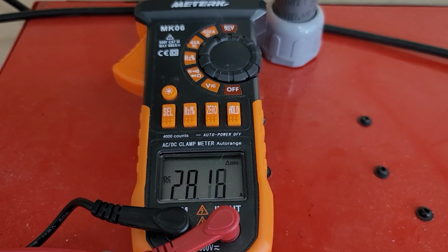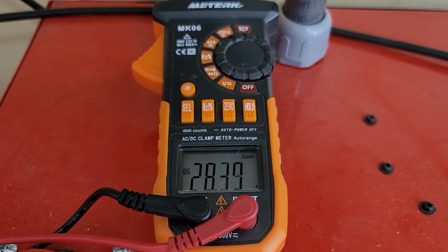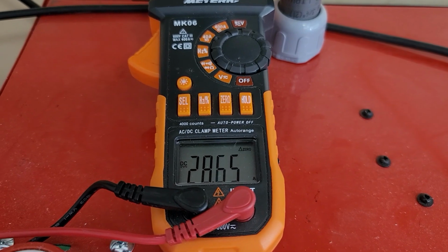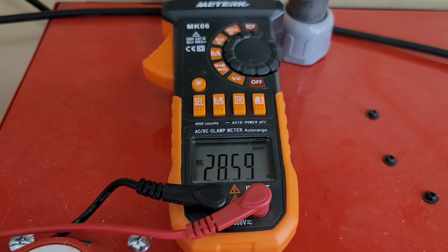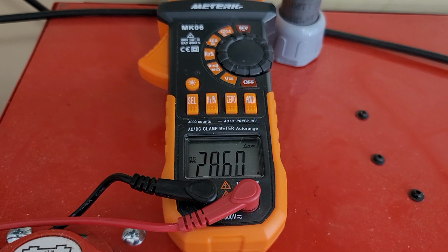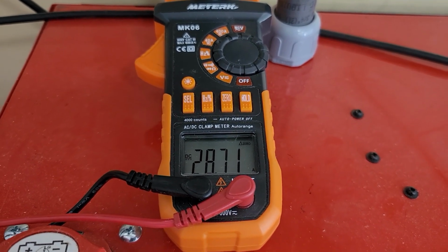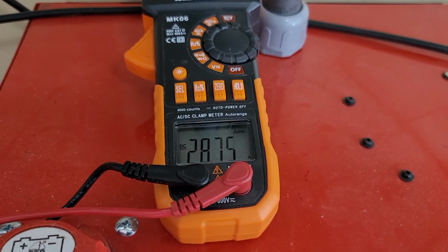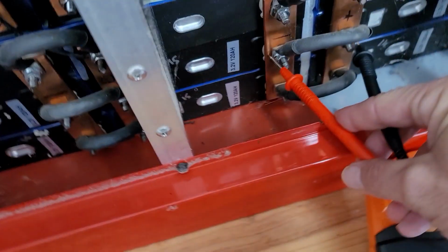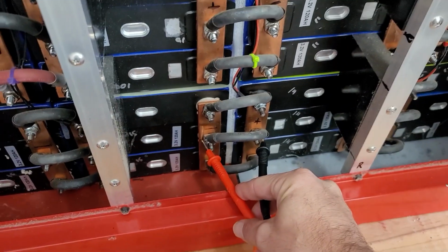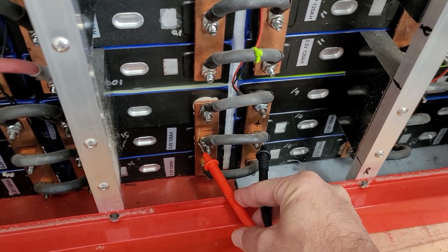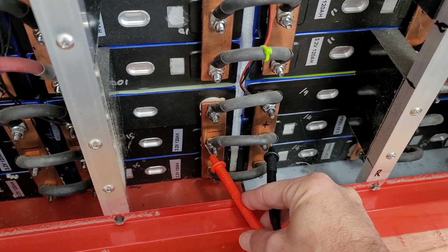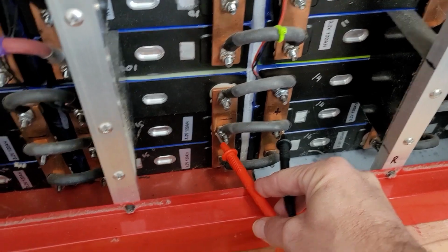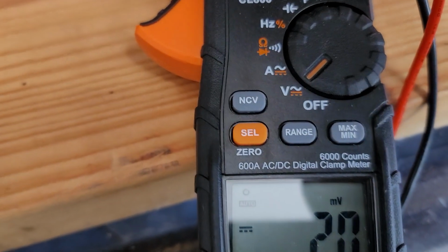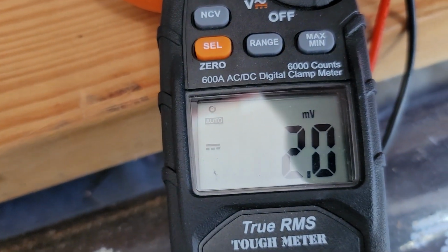At this moment we are up at 28 amp charge for this Powerwall. Let's go take a look at the same spot and see if the voltage drop increased. Here we are, on a connection between module 14 and 15, and the current voltage drop at those 28 amps is 2 millivolts.